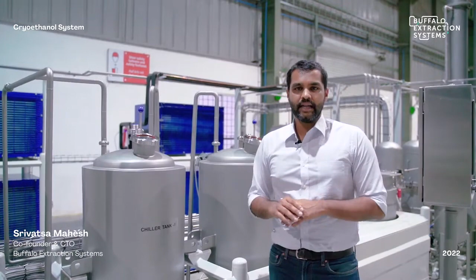There are two pre-chiller skids, where one pre-chiller skid tank is used as a process solvent, and the second chilling tank is used as a utility solvent. That means one tank is used to be in contact with the biomass and extract the oils from it, and the other tank is used for all the jacketing of the centrifuge, so that during the process of extraction there is no increase in temperature and the process temperature is maintained in a very stable manner.